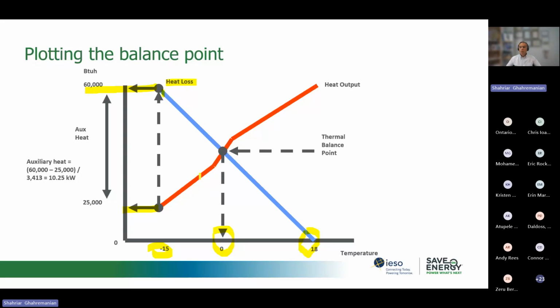Then we see there is a big difference between the amount of heat my building needs, 60,000 BTU per hour, or 17 or 18 kilowatts, and what the heat pump can supply, 25,000 BTU per hour, which is almost 7 to 8 kilowatts. That means I need about 10 kilowatts of extra heating supplied to my building. So this shows us how much supplement, auxiliary, or additional heat needs to be supplied by extra sources. So this is the point.